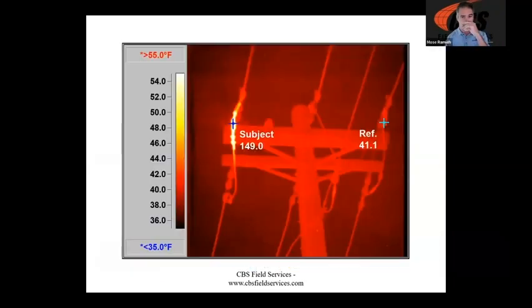A lot of folks are out there running their lines, checking to make sure that they don't have any bad crimps or other connections out there. And once again, this is really applicable whether you've got an outdoor substation or a facility with several different types of indoor substations. It's a little hard sometimes to scan that indoor equipment, and there are a lot of other safety practices that go around that.